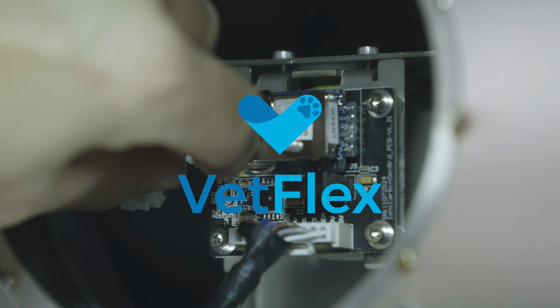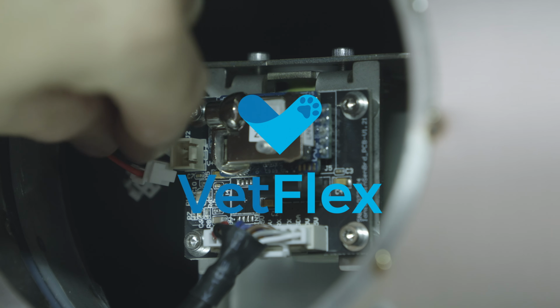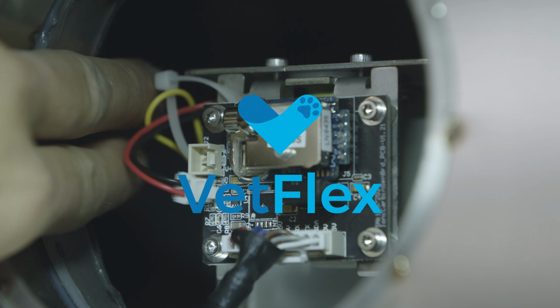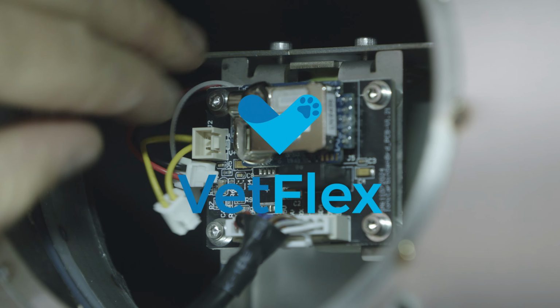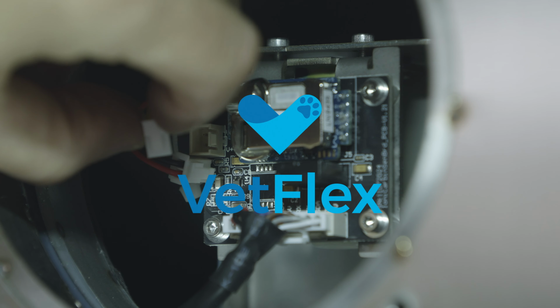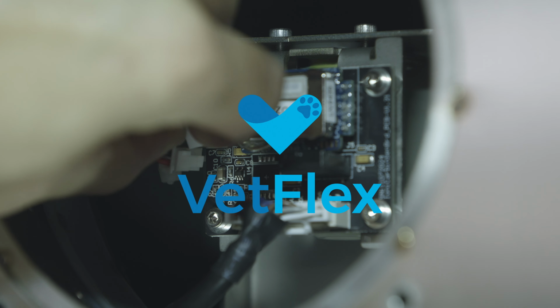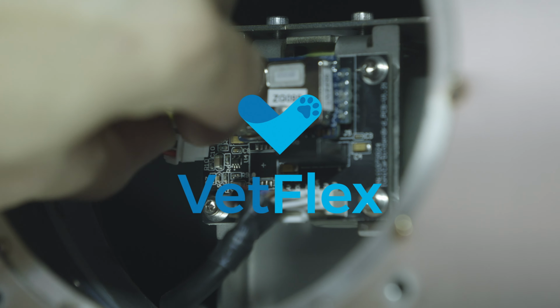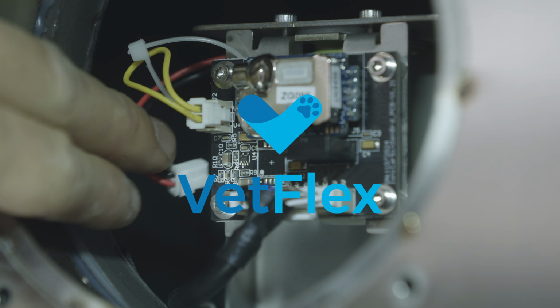A factory reset may be needed if oxygen is not holding steady at the preset parameters, or similar, after attempting calibration. Please note, make sure to consult your VetFlex representative before doing either of these troubleshooting steps, as it may void any warranty or service plan coverage.